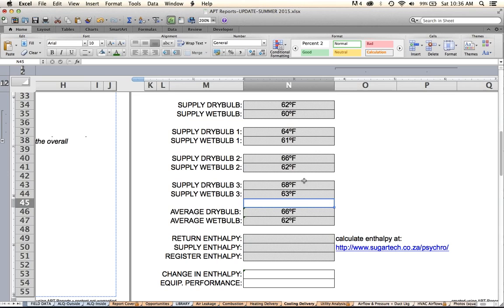leakage at 25 pascals, what does that mean to my client? How can they, what are they supposed to do with that? You could say, oh, it's 15 or 22 CFM per 100 square feet. What does that mean? How do I get this language to communicate to my client, to motivate them to spend money to fix the problem, to make their life better? That is the goal. The goal is not numbers. Numbers are only a tool, so they can be used for the power of good or for the power of evil.